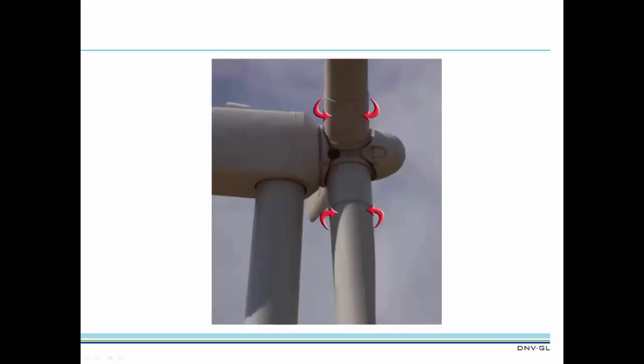Constant rotor speed is achieved by pitching the blades progressively towards feather as the wind speed rises. Pitching the blades ensures that despite the increasing wind speed, the net aerodynamic torque about the rotor axis is held at a constant value equal to the torque demand. With torque balanced, rotor speed, and therefore power output, both remain constant.